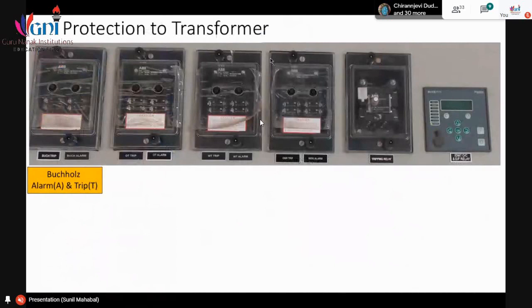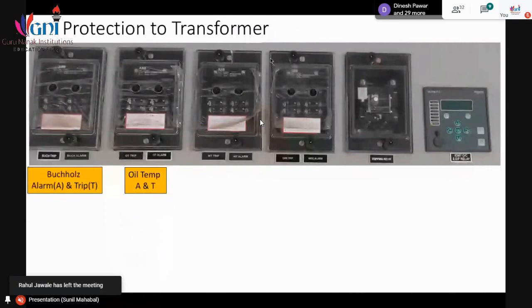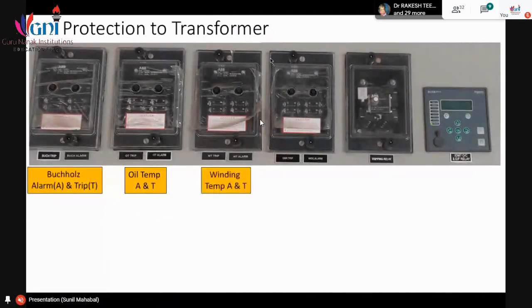Then there is oil temperature alarm as well as trip. It will first give you an alarm, and if you don't act on that alarm, then it will trip the transformer, the incoming of the transformer. Then there is winding temperature trip and winding temperature alarm. Both are there.